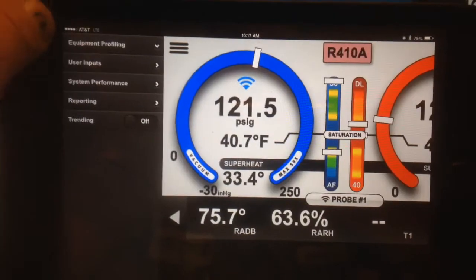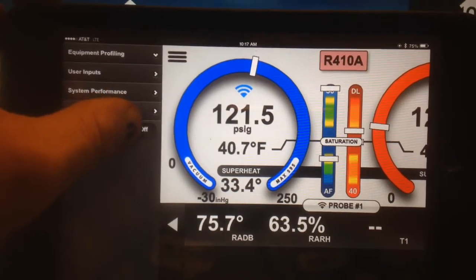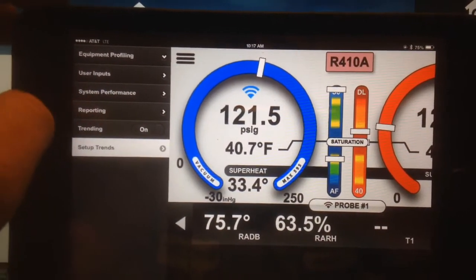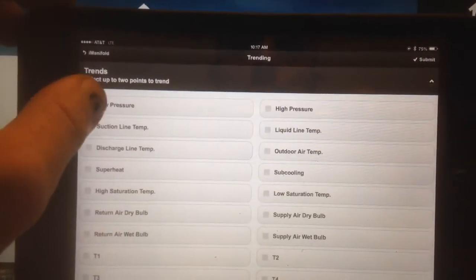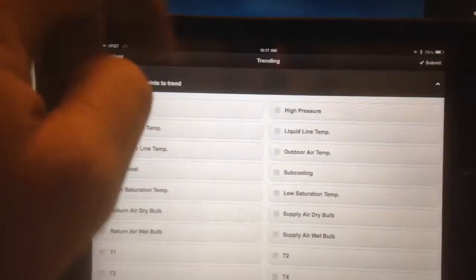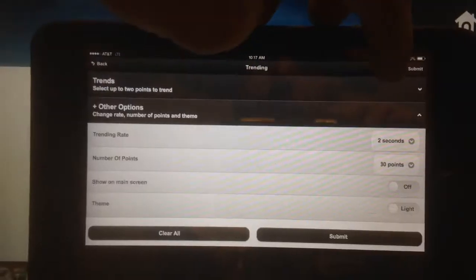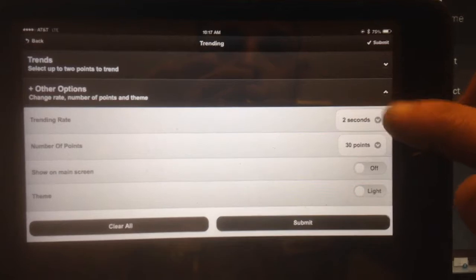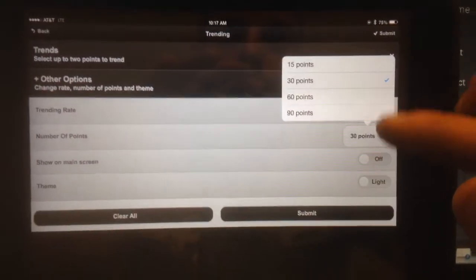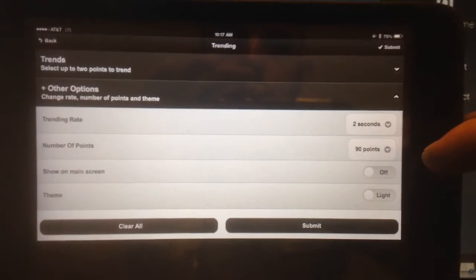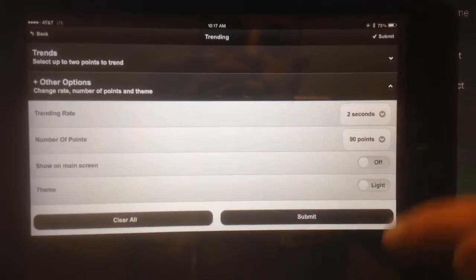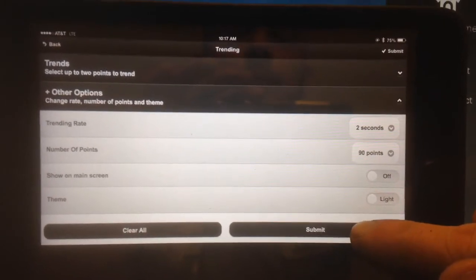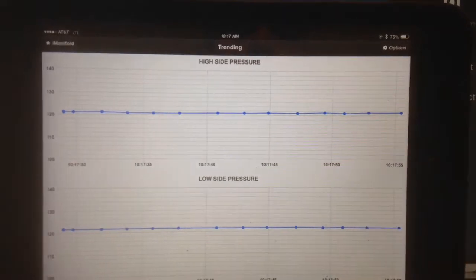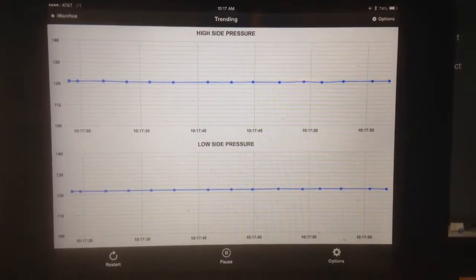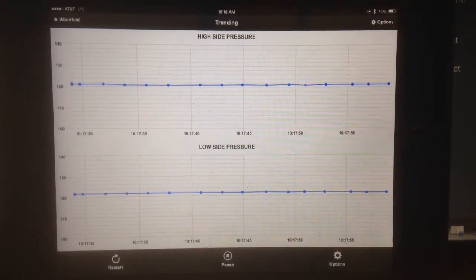Before we turn the system on, we're going to go over here to trending. Going to set up trends. For fun, we're going to do the pressure low, pressure high, and set this up for every 2 seconds. And we're going to show 90 points of data on the screen. And we're going to submit that. So there we are showing our trends.